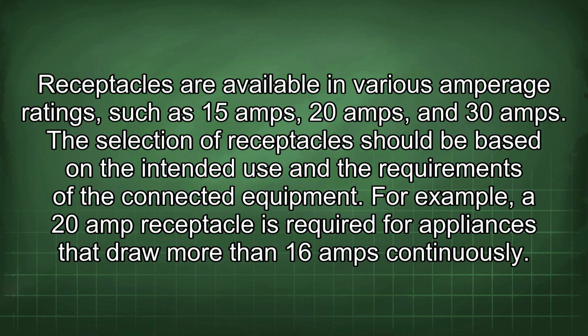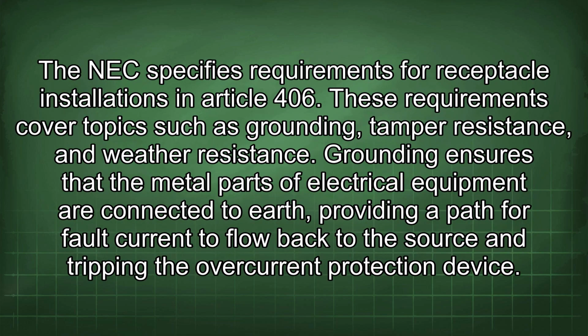Receptacles are available in various amperage ratings, such as 15 amps, 20 amps, and 30 amps. The selection of receptacles should be based on the intended use and the requirements of the connected equipment. For example, a 20 amp receptacle is required for appliances that draw more than 16 amps continuously. The NEC specifies requirements for receptacle installations in Article 406. These requirements cover topics such as grounding, tamper resistance, and weather resistance.